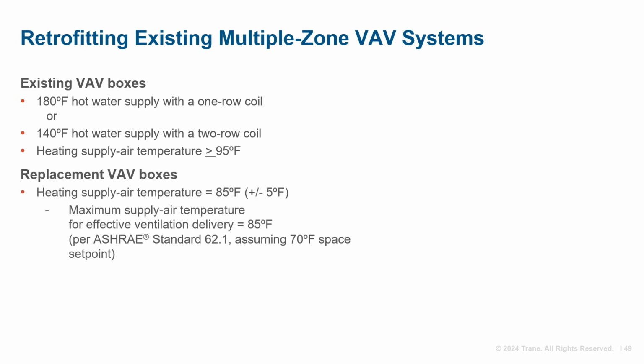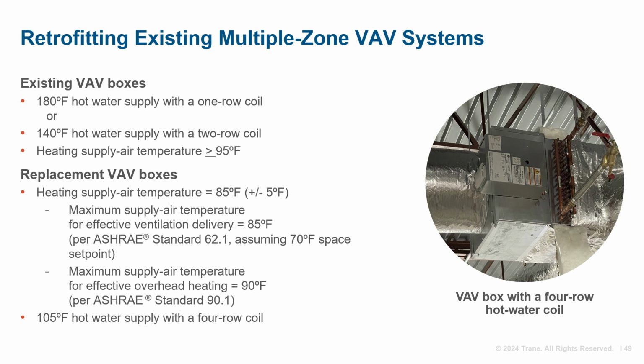In most VAV systems, heated air is supplied through ceiling diffusers. If supply air temperature is above 85 degrees, this will reduce the effectiveness of delivering ventilation to the breathing zone and will require 20% more outdoor air to the zone. Increasing the ventilation requirement in winter by 20% is a big energy increase if the zone is not already overventilated. ASHRAE 90.1 also prescribes supply air temperature not to be above 90 degrees when delivered from ceiling to effectively deliver the heat to the zone. A heating supply air temperature in the 80s in most cases will require 105 degree water with 4-row heating coils in the VAV boxes.